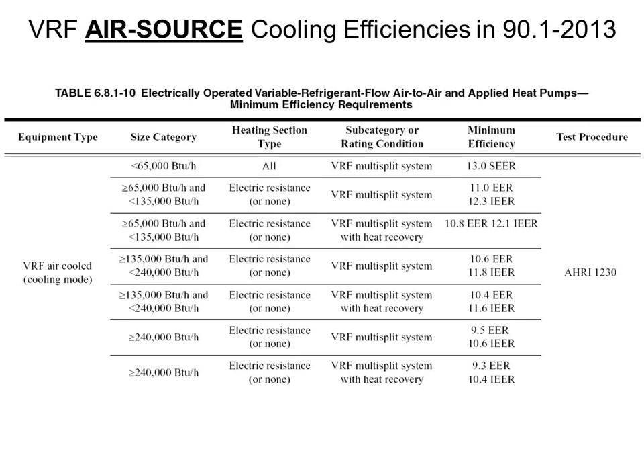All right, let's talk about ASHRAE Standard 90.1 a little bit. Starting with 90.1 2010, we started putting in categories for VRF systems in there. Prior to that, when you were looking for ASHRAE compliance or code compliance, you basically just used the DX split system rating, and it was very easy to hit that with a VRF system. Now VRF has its own category and its own set of 3 tables in the 90.1 book, and those efficiencies, you'll note, are often required to be a little bit higher than other DX systems.